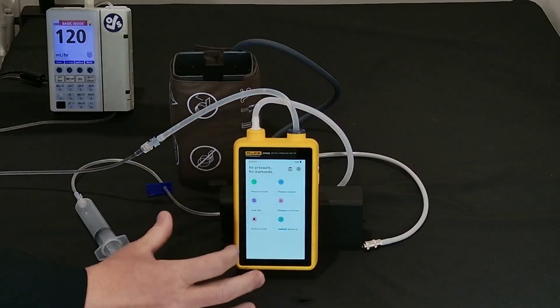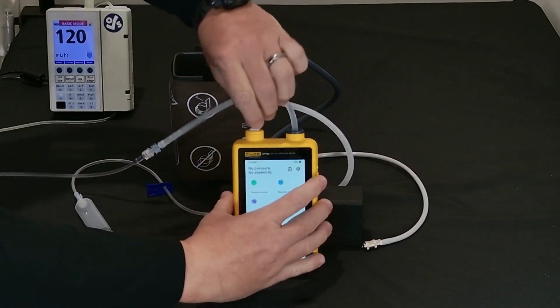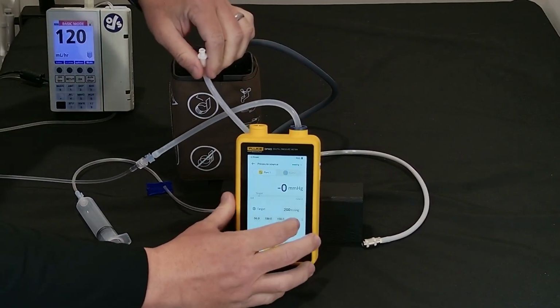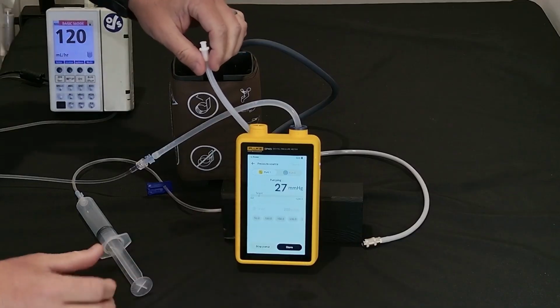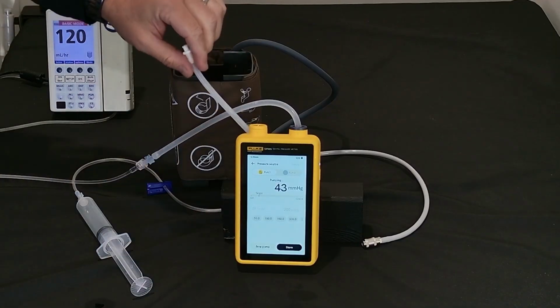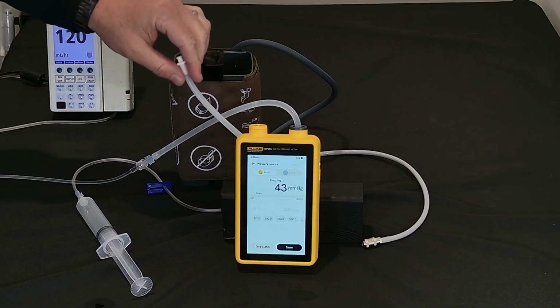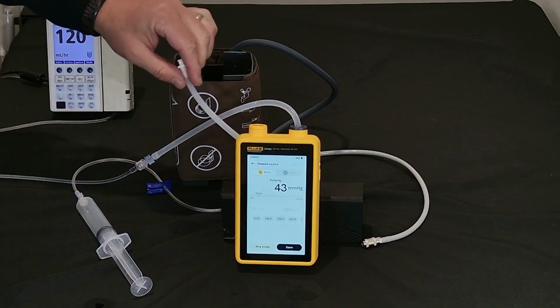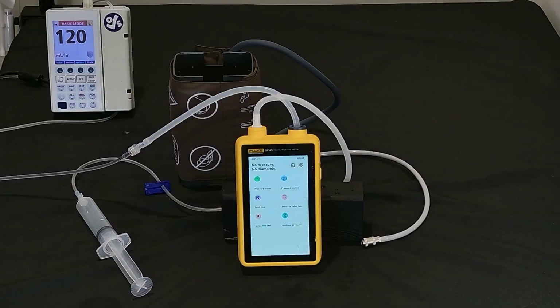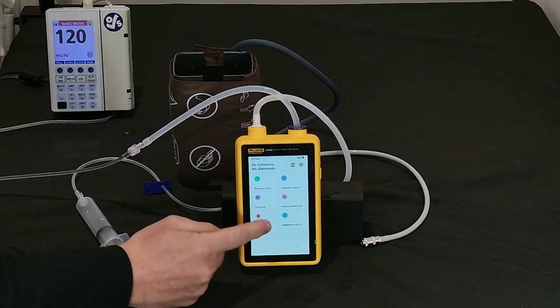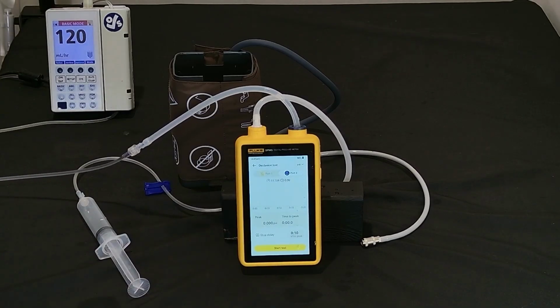You can unhook your line. You can run your pressure source to a very high value. Start your pump, and that'll blow out a little bit of the water that you've accidentally put in your port 1. So here we have our pump running. Now we'll go to our occlusion test, and we'll start our test.